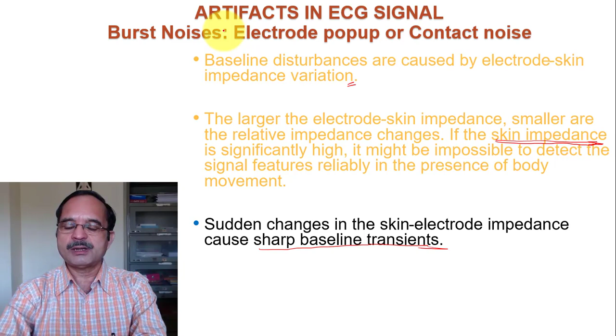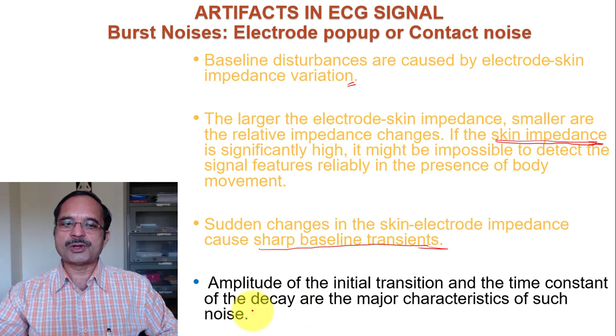Sudden changes in the skin electrode impedance cause sharp baseline wanders, baseline transients. So suddenly the baseline can move up or down because of the sudden changes in the skin electrode impedance. There are various techniques to reduce this skin electrode impedance. Different types of jellies are used. So that I think we have discussed in the electrode topic in the first unit. Okay. Amplitude of the initial transition and the time constant of the decay are the major characteristics of such noise.